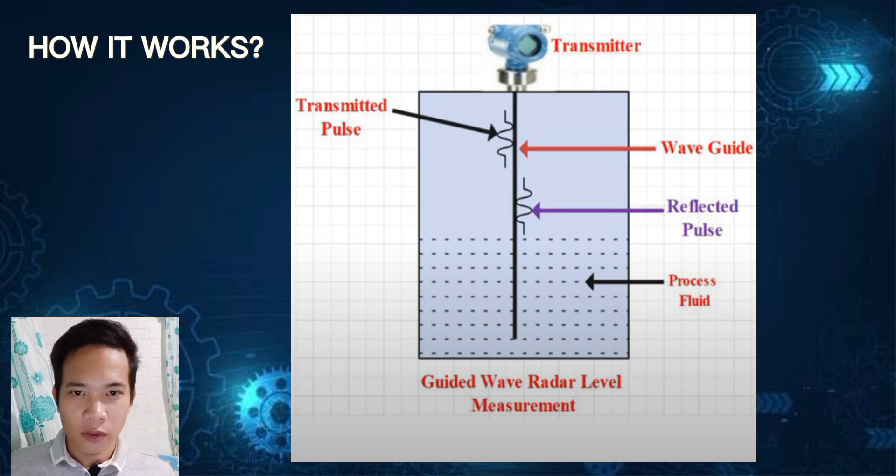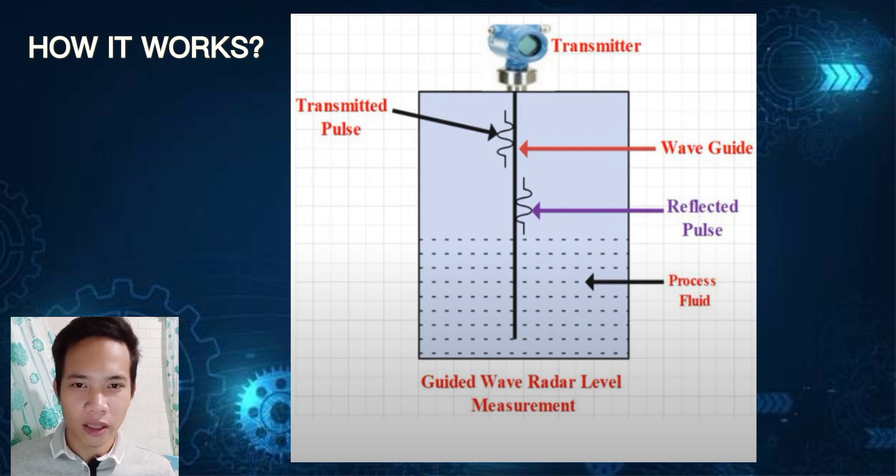The time it takes for the signal to return is measured. The sensor measures the time delay between sending the signal and receiving the reflected signal. Using the known speed of light in the waveguide probe, which is constant, the sensor calculates the distance from probe tip to the material surface.